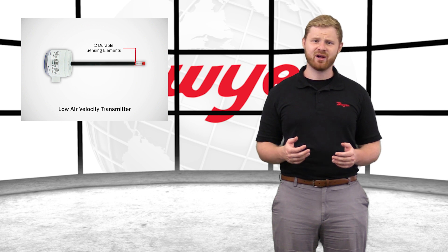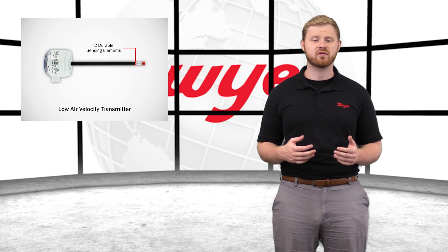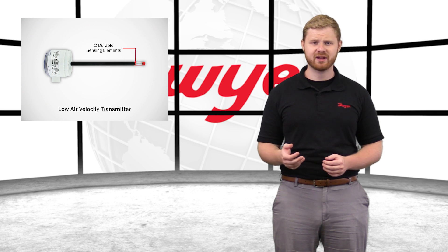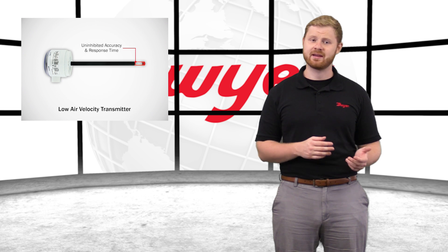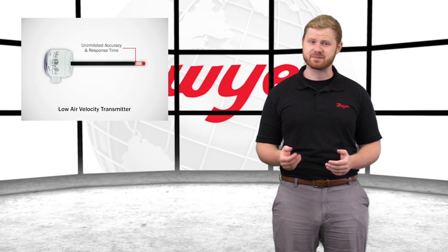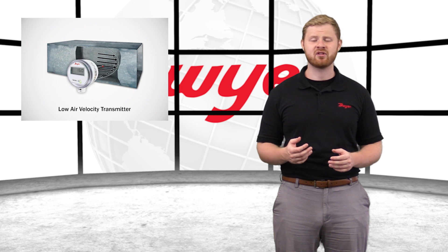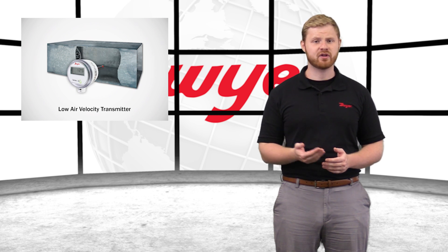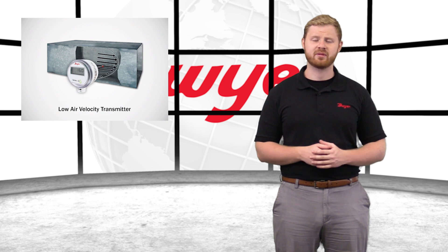The Series AVUL is equipped with two sensing elements protected with an engineered conformal coating to ensure durability and longevity. The size of the sensing elements reduces the likelihood of contamination, which can reduce the response time and accuracy of the unit. The heat loss between the elements is measured as air flows over them, which is accurately converted into air velocity or volumetric airflow.